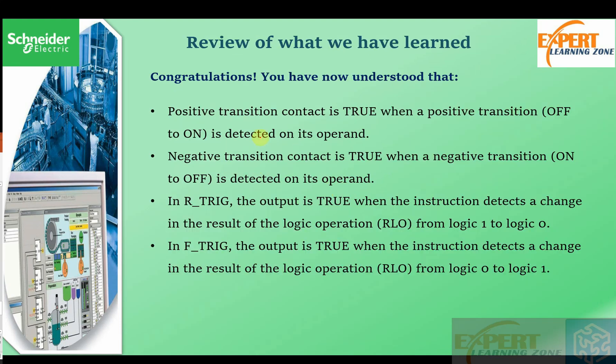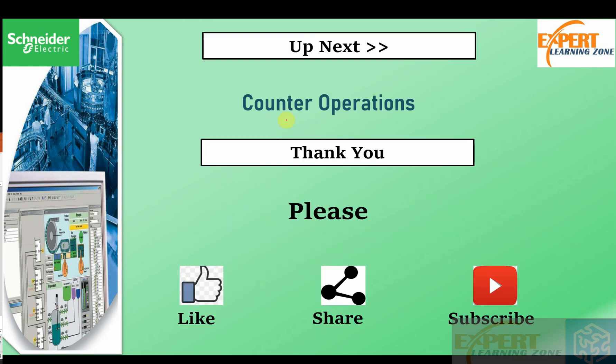Let's review what we have learned. The positive transition contact is true when a positive transition off-to-on is detected on its operand. For the rising edge trigger, the output is true when the instruction detects a change in the logic result from zero to one. For the falling edge trigger, the output is true when the instruction detects a change in the logic result from one to zero.